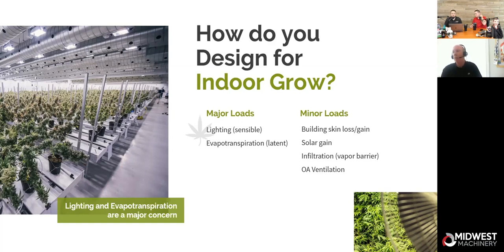The further south you go, take the Gulf states, the lower Midwest, we have humidity for four or five months of the year. So if you're bringing outside air in the middle of summer when it's hot and humid in Missouri, how's that going to dehumidify your space? We always say this isn't a commercial building required to meet an ASHRAE 62 code ventilation requirement so we don't choke on our own fumes. It's an industrial process, you have few people in there, and what do plants give off when they grow? Oxygen. So the oxygen content inside the grow room may be better than outside it.